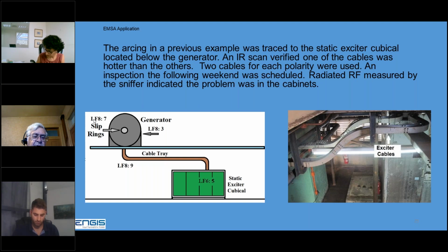LF is the scale that we use, the range. 8 is the gain, 7 is the reading. So on the slip rings, we got a reading of 7. On the generator itself, we got a reading of 3. So the slip ring may be sparking. We went underneath the generator and the reading was now 9. Well, it only goes up to 10, so we had to cut the gain down from 8 to 6, and we got a reading of 5. So the reading got higher as we went down to the static exciter cubicle. It was not the slip rings that was sparking, it was in the static exciter.